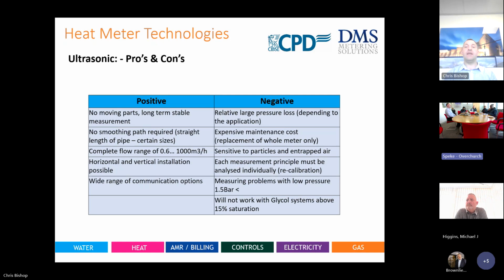Sensitive to particles and entrapped air. So, oxygen inside the system happens. You get trapped air in systems that aren't purged correctly, that aren't commissioned correctly, sometimes not commissioned at all. The meter knows this. If there's trapped air inside dead legs or the meter chamber, or just flowing around the system naturally, the meter can distort its flow rate over time, and that would also cause lower readings within the meter itself. So ultrasonics are more susceptible to trapped air. So it's just keeping that note in case it's relevant for the application selection.